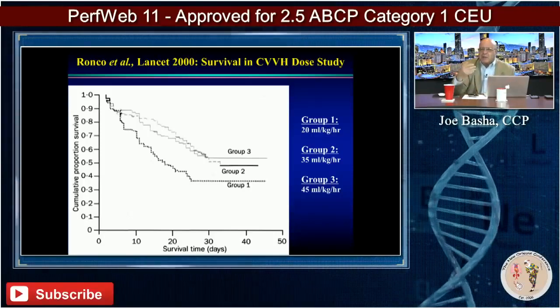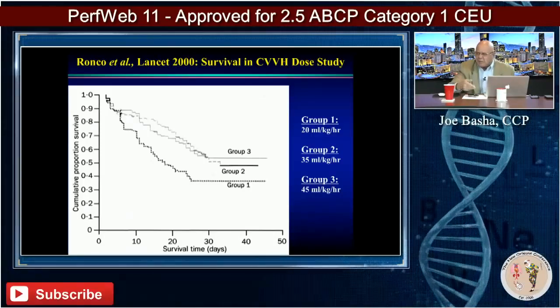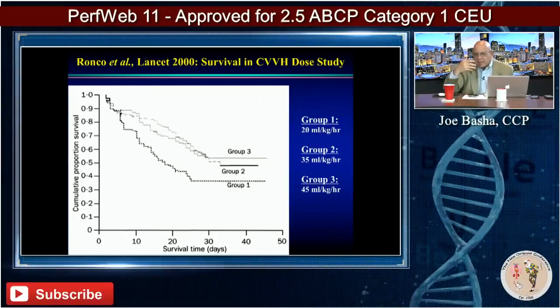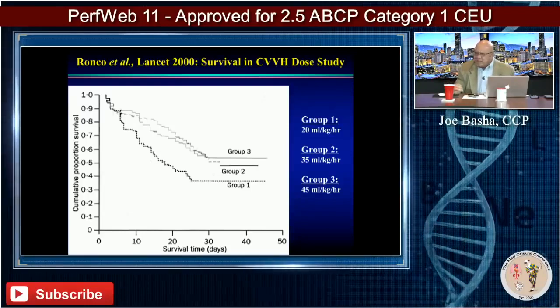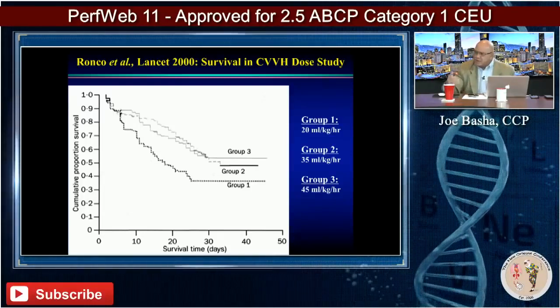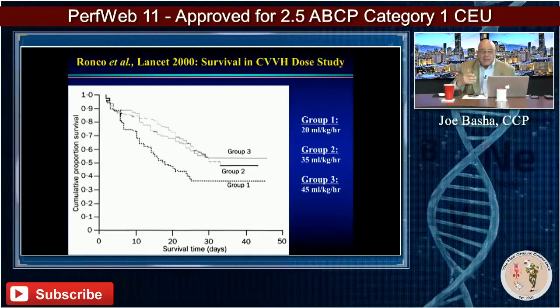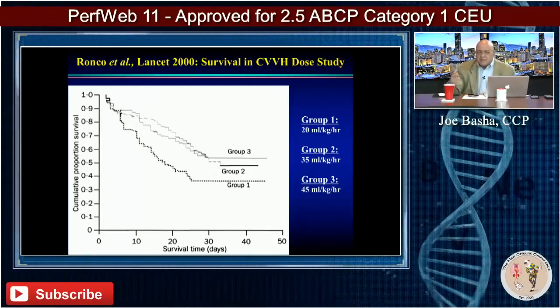And that's how much effluent is being removed. Now you're replacing it with the replacement fluid, but it's just how they do it in the nephrology world. It's very different than us, but the dose is actually your effluent dose. That's what it's measuring. But if you need it to be zero balance, then your replacement is going to be exactly equal to that. If you want to remove fluid from the patient, for example, then you're going to have a patient fluid removal. So you may be giving back 3,000, but removing 3,200, which means you're taking 200 off for that hour. So your effluent dose is still going to be considered that 3,200, not 3,000.